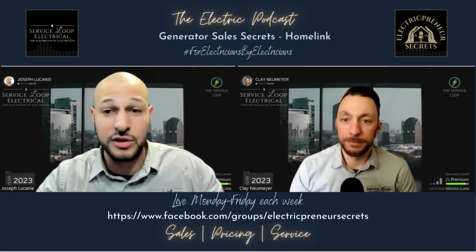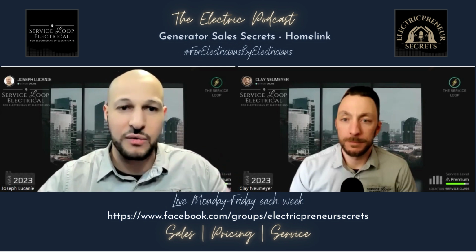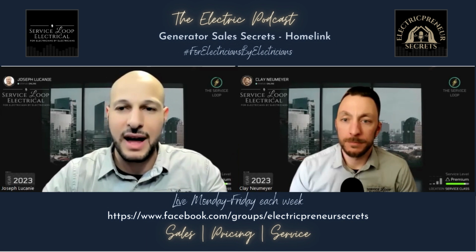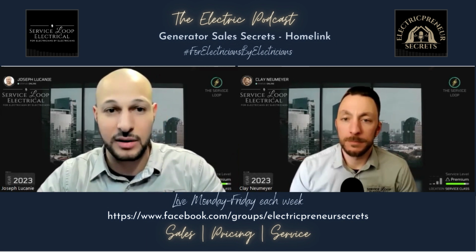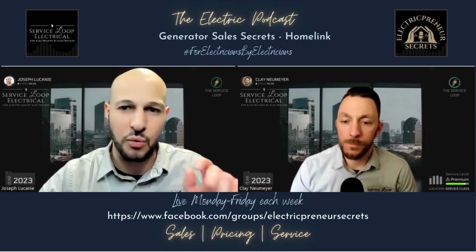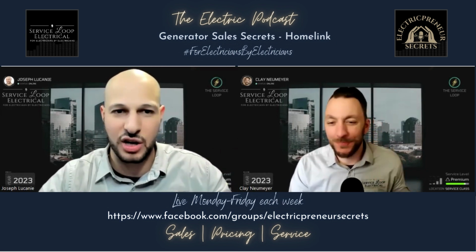But if you lose power, you still need a generator. So what do you do? This is one of the best ways, because you can tell them, we can start you off with this particular system. And I'm going to go into the verbiage of how we describe it, but I'm just speaking layman's terms. We would describe that this system is allowing them to have that generator backup battery power. They'll have to use it portable for now. But the best part about this is that it's upgradable. All it takes is one additional relay to be installed into it, and it converts to an ATS, and it'll carry up to an 11 kW automatic generator.